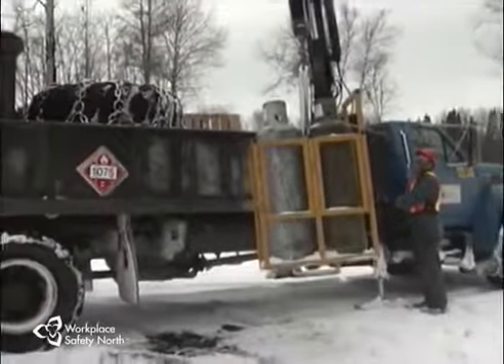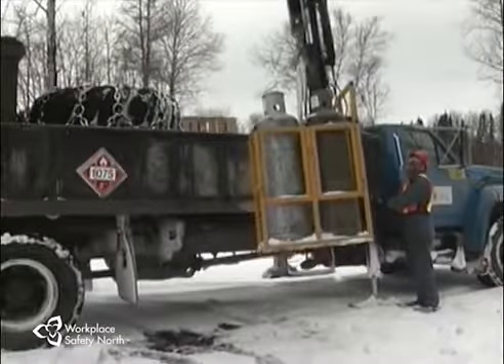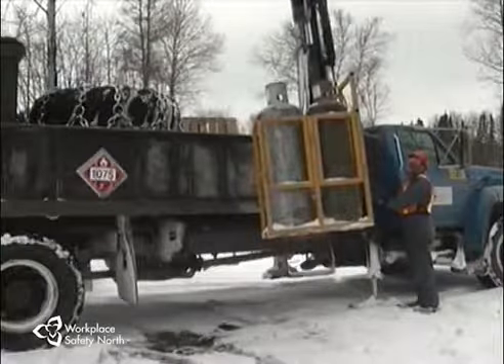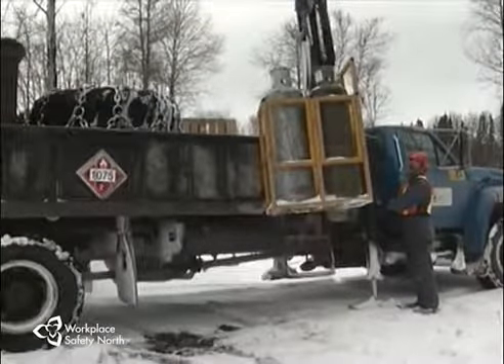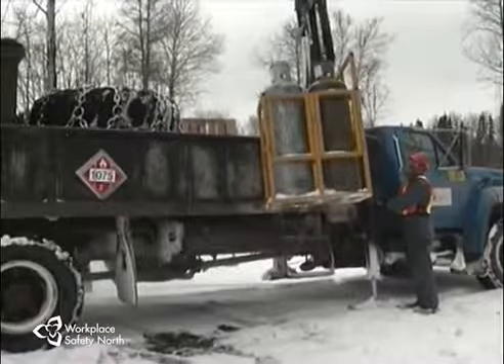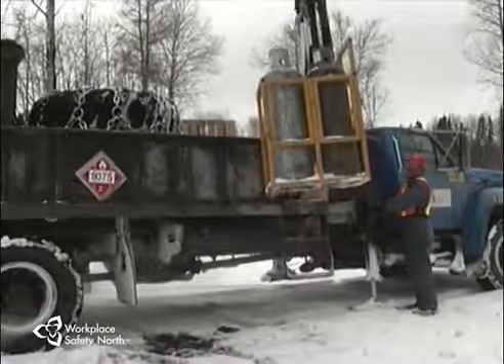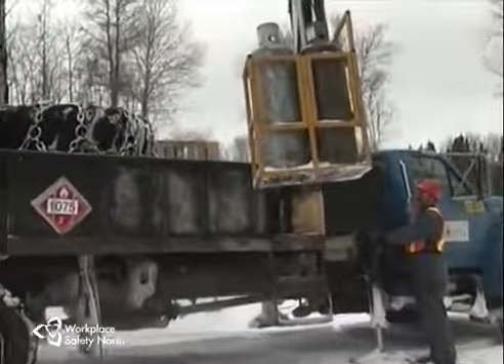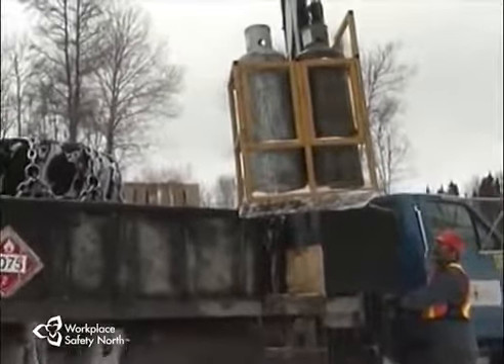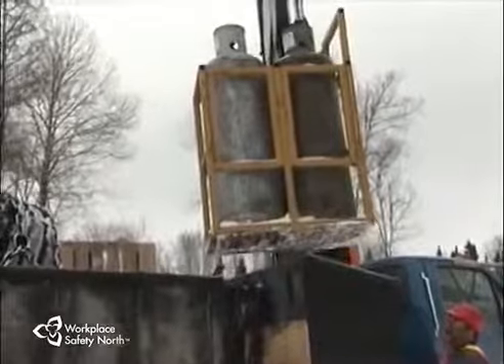An open vehicle is one in which the cylinder is plainly visible from the outside. If not, the vehicle must be properly labeled with warning signs that propane is being carried. Placards on all four sides of a vehicle are necessary when transporting more than 5 cylinders of any size or more than 500 kilograms or 1,100 pounds gross weight.